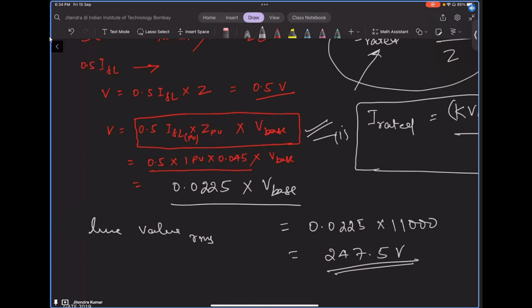So that much voltage you are applying, you have to apply at this particular condition during this kind of test, right? However, the rating of this primary winding is 11 kV and we are operating at 247.5 volt only. So we can operate at any value, but rating will be maximum, right? As one guy said, rating is the maximum value, right? So I hope this is clear to you guys. Any doubt in this part? No sir, no. Okay, great.